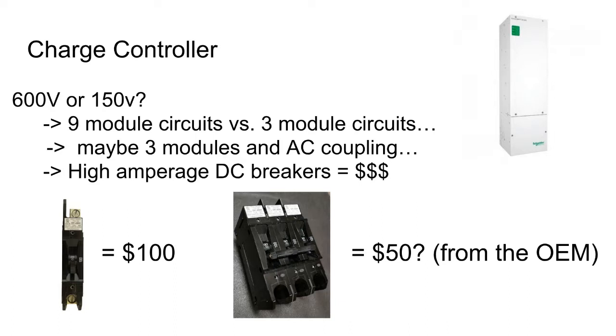So you go to Schneider and say, okay, I'm buying your $1,000 charge controller. And they say, well, you need a 100 amp breaker. You say, okay, give me a 100 amp DC breaker. They'll sell you each 100 amp breaker for $100 each. That adds 10% to the cost of the charge controller.